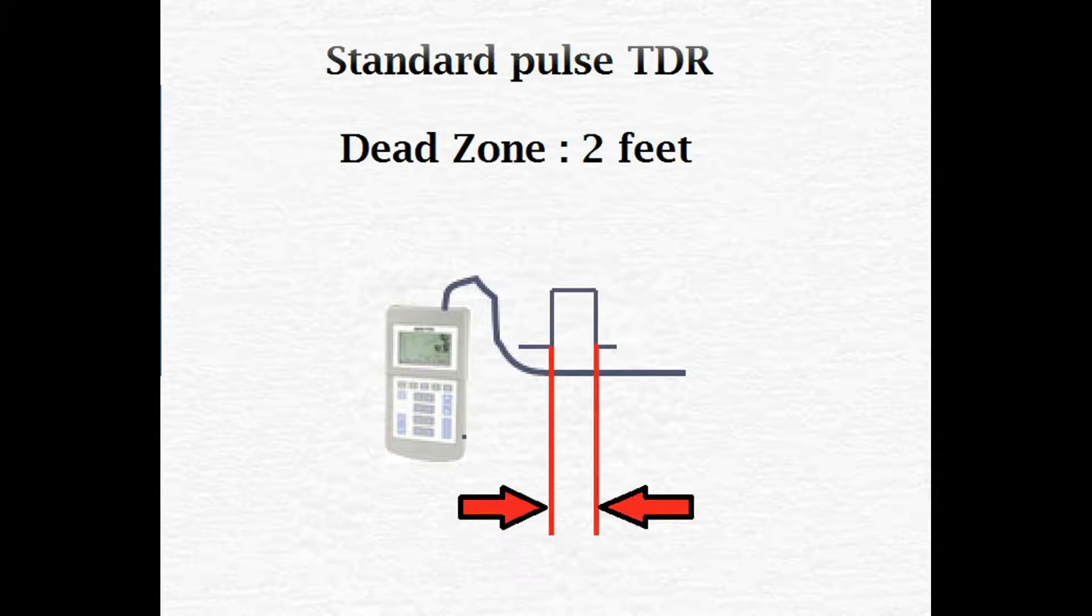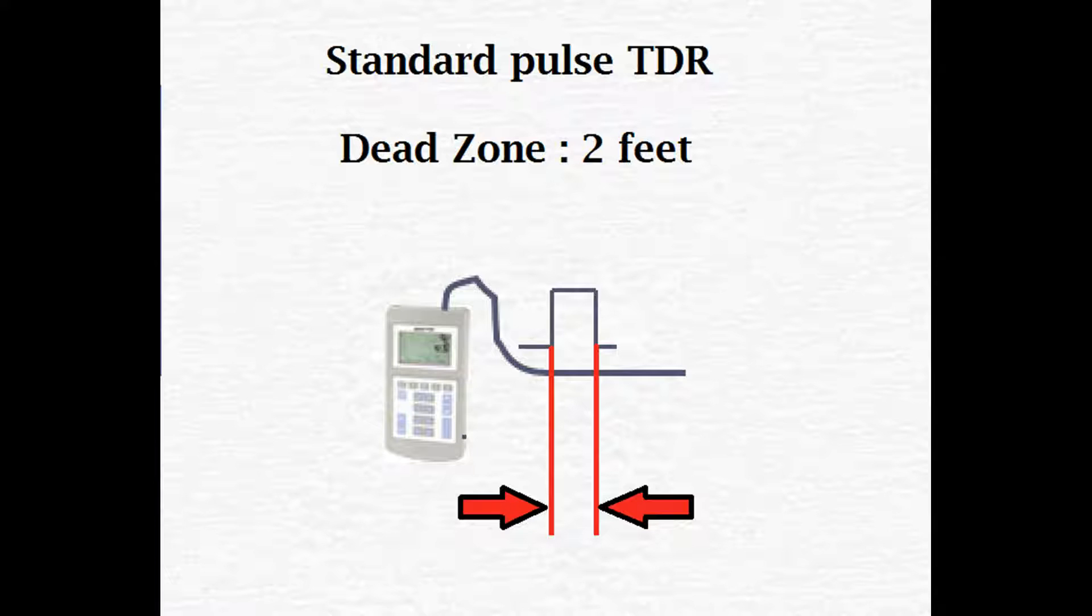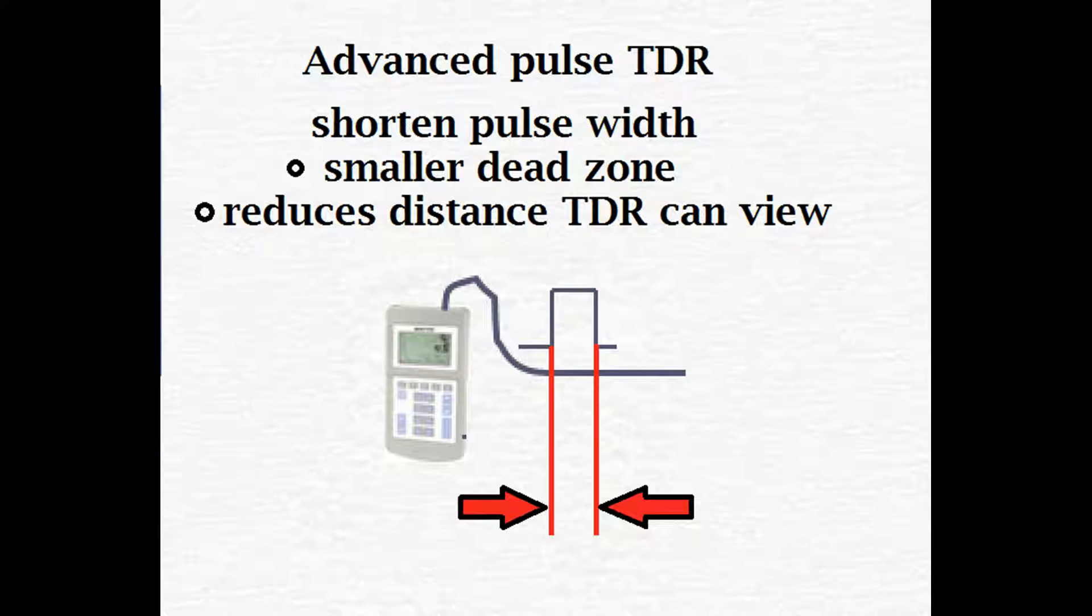The other problem is the actual pulse itself. The test set receiver is turned off during the width of the pulse. So on a standard TDR, this effectively gives you a dead zone where you can't see faults within the first two feet of the wire. More advanced TDRs let you change the width of this pulse. You can shorten it, giving yourself a smaller dead zone, but this also reduces the length of cable you can check.